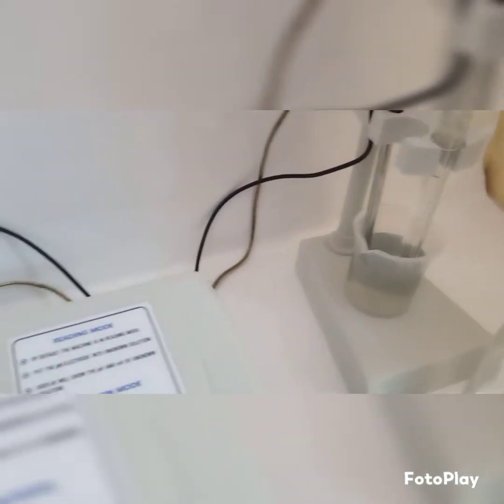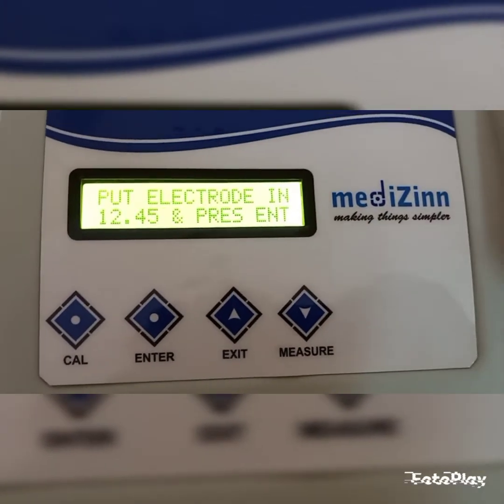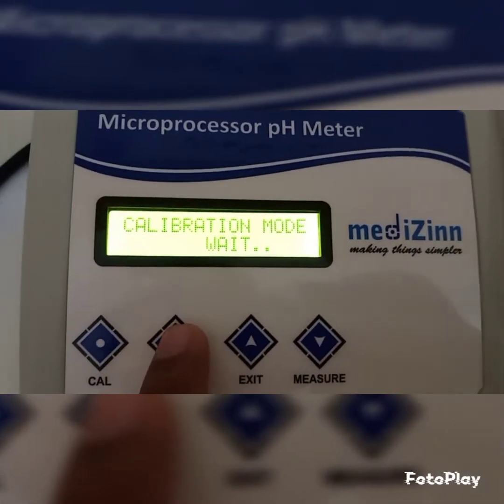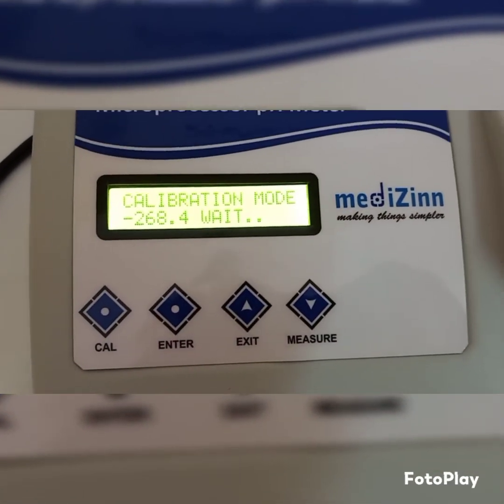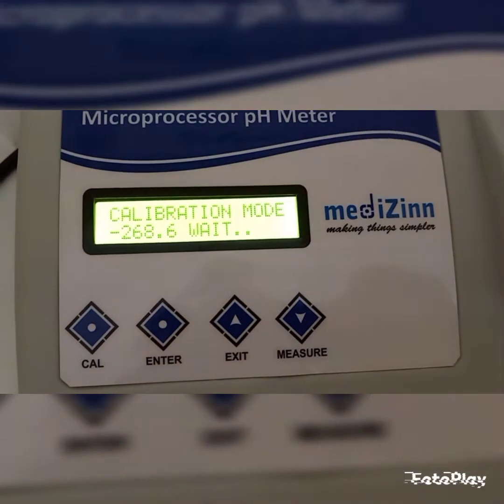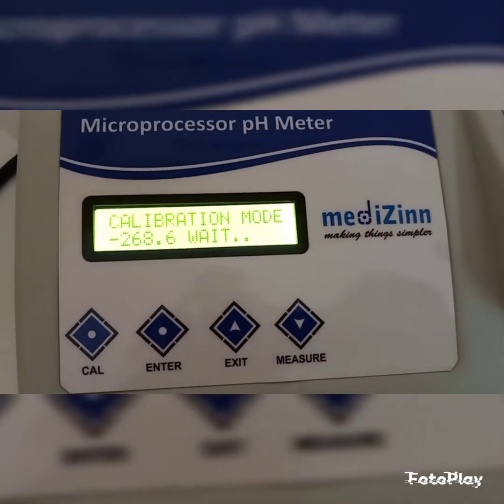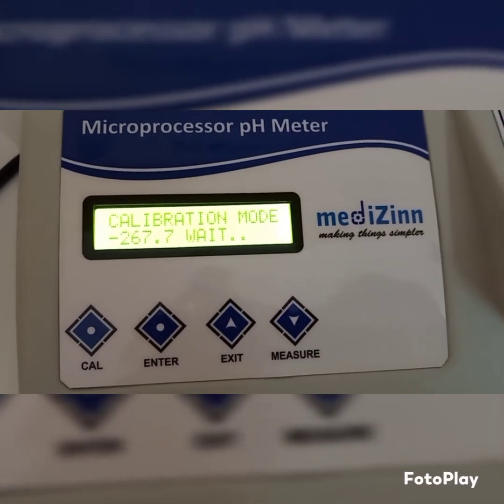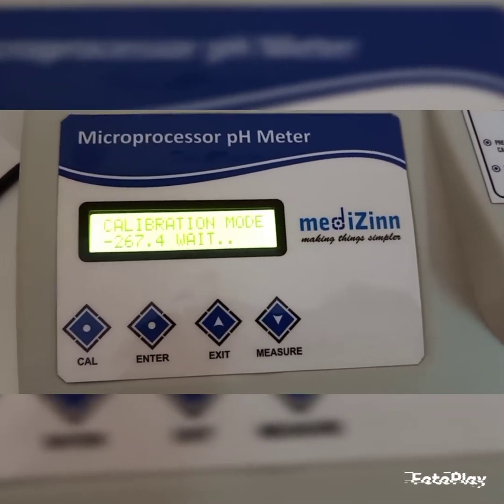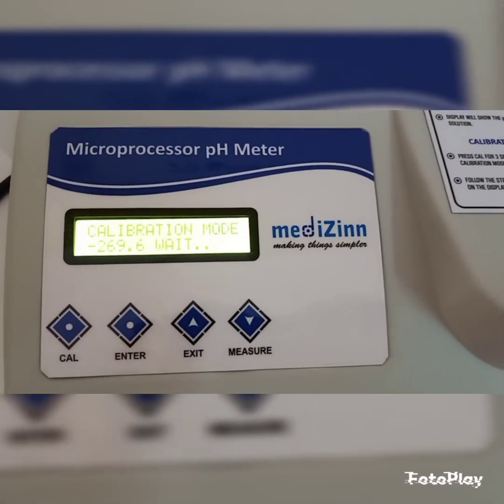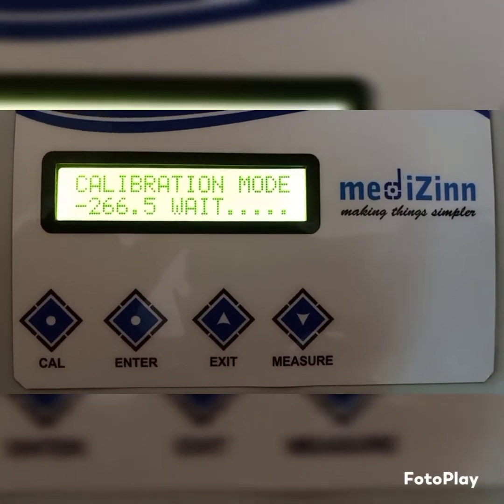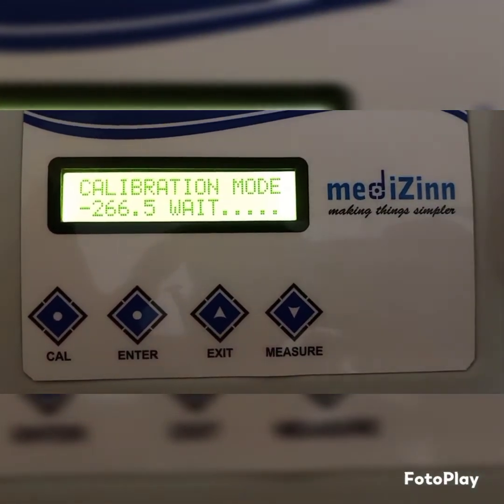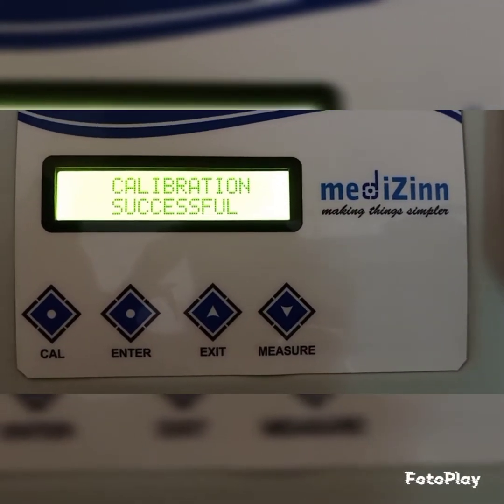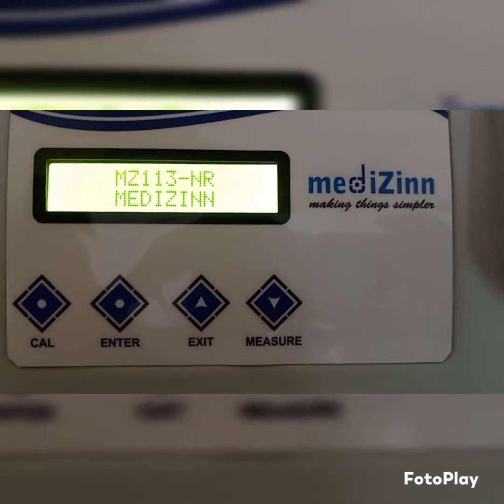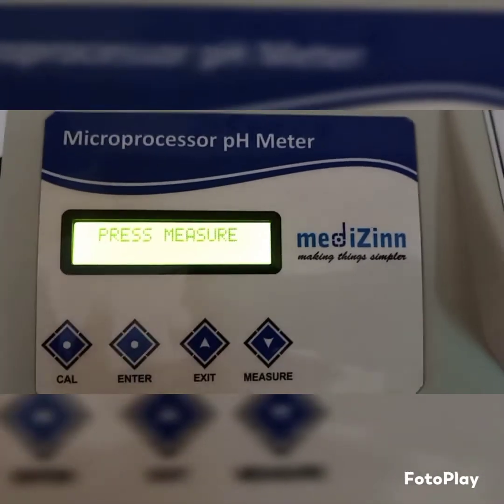Now put electrode and temperature probe into 12.45 pH buffer and press enter key. Again analog value is there, that is in the negative, that indicates that the buffer is greater than 7 pH. Now again we have to wait for approximate 2 minutes for the calibration process over. 12.45 pH done, calibration successful. Now machine automatically comes to the measurement mode.